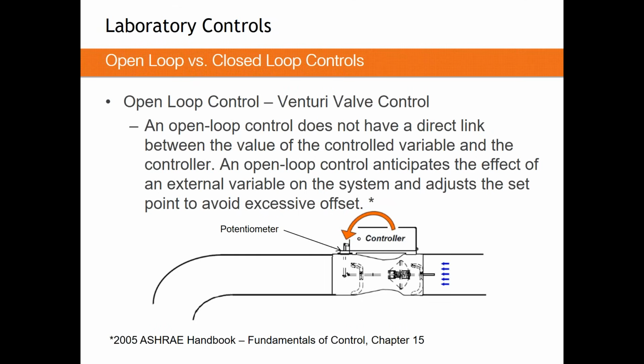Now that brings us to open loop controls. This is the style we use for a Venturi valve. We call it open loop because we don't directly measure the variable we are trying to control. In a Venturi valve, the value we're trying to control is airflow, but the value we measure is position. So there's no direct feedback of that measured value. We still have an understanding of what airflow we're at, and we can still measure and control it, but there's no direct link.